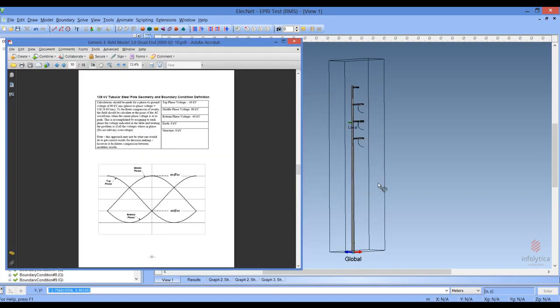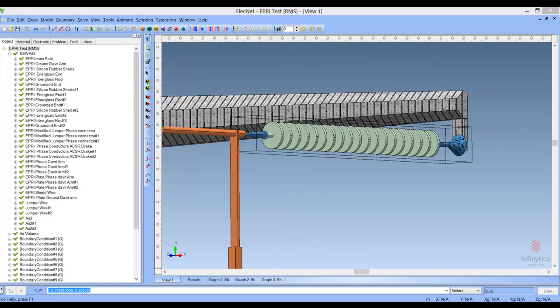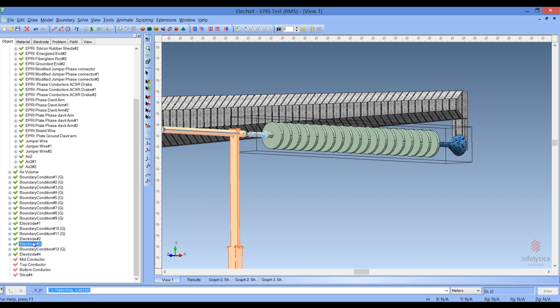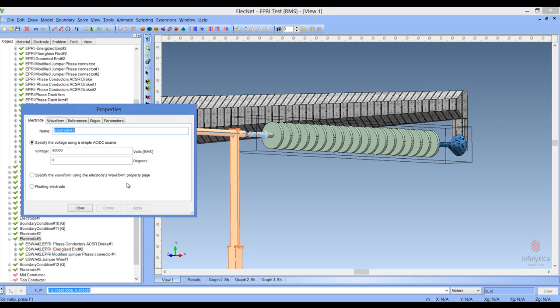In the EPRI specification, the central arm will be the one carrying the high potential. The parts that are of interest are shown here: the ground fitting set to ground potential as indicated by the texture, and the energized electrode formed by the phase conductors, the energized end fitting, the jumper phase connector, and the jumper wire. All these form the same part of the electrode, and as you can see, 80,000 volts is applied to those components.